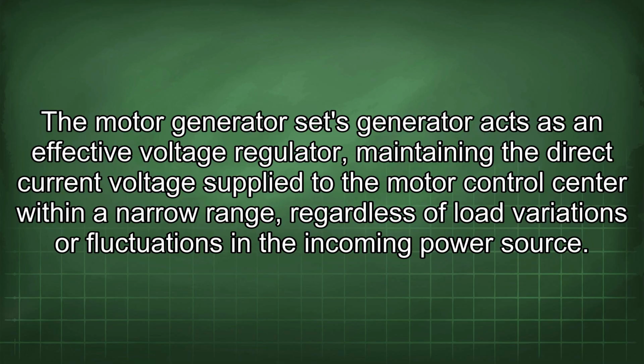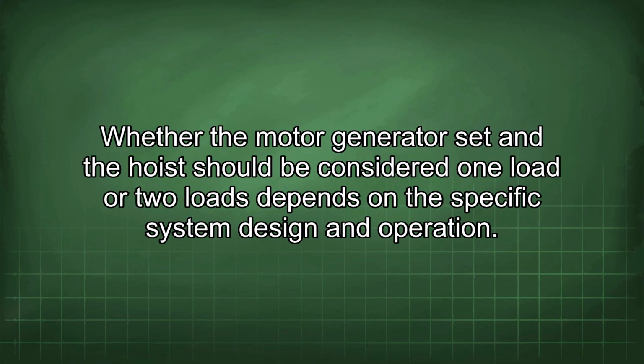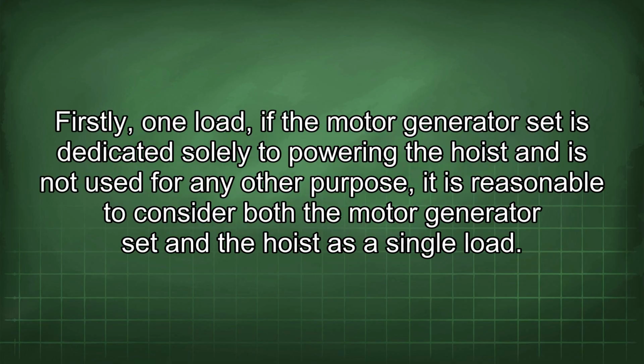The motor generator set's generator acts as an effective voltage regulator, maintaining the direct current voltage supplied to the motor control center within a narrow range regardless of load variations or fluctuations in the incoming power source. Whether the motor generator set and the hoist should be considered one load or two loads depends on the specific system design and operation. Firstly, one load.